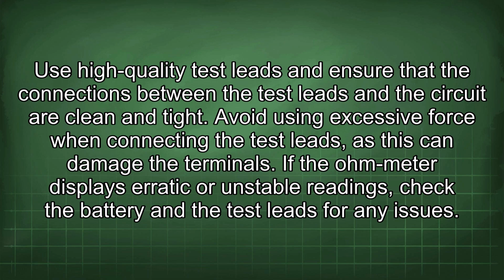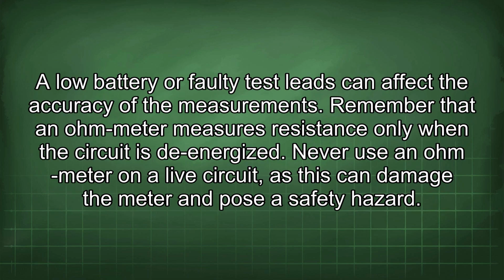Avoid using excessive force when connecting the test leads, as this can damage the terminals. If the Ohm-Meter displays erratic or unstable readings, check the battery and the test leads for any issues. A low battery or faulty test leads can affect the accuracy of the measurements.